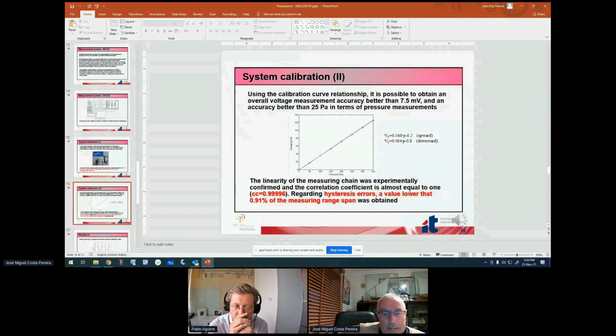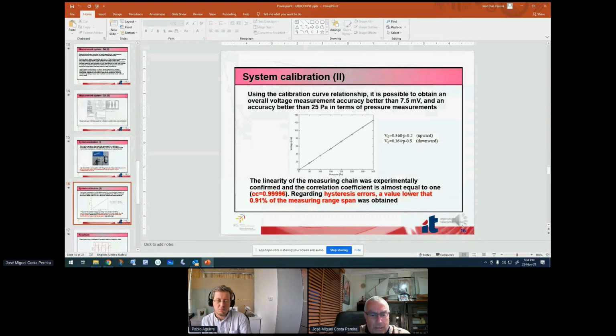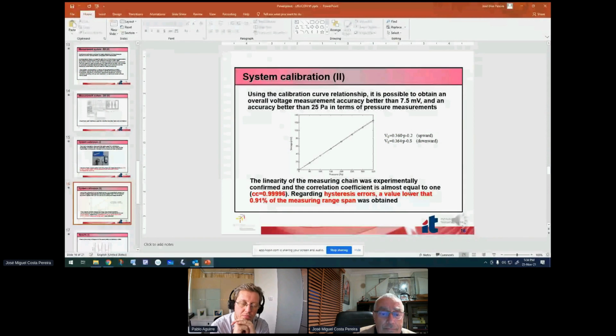Here we have some results regarding linearity and hysteresis. We have an almost linear system. The correlation coefficient is very high, almost equal to 1. Regarding hysteresis errors, a value lower than 0.91% of the measuring range span was obtained. In this graphic, on the x-axis we have pressure values, and on the vertical axis we have the voltage associated with the pressure values. So this is the characteristic of the input chain of the equipment.